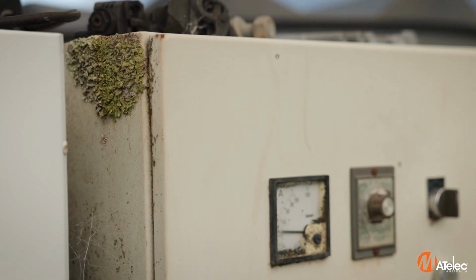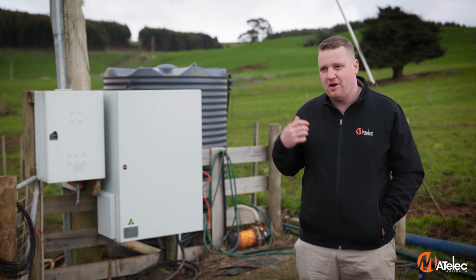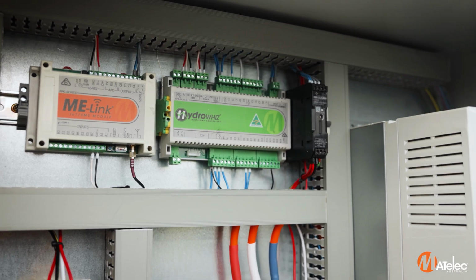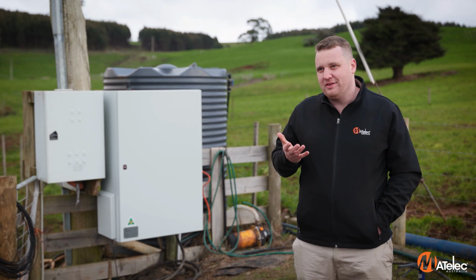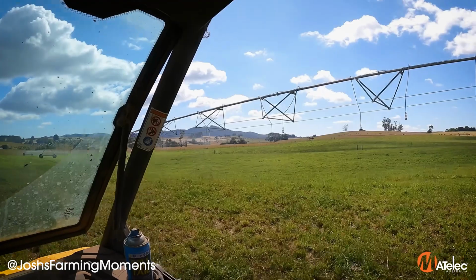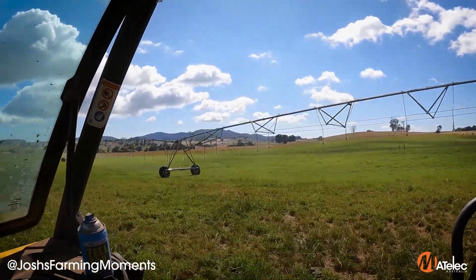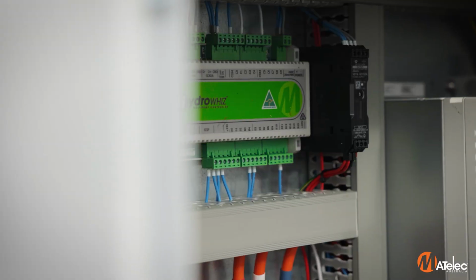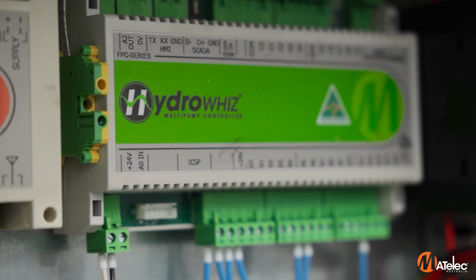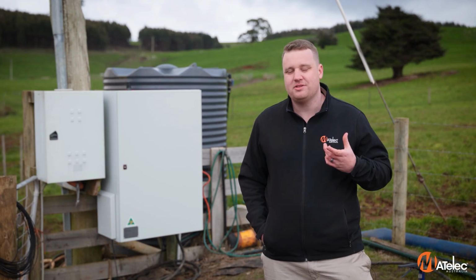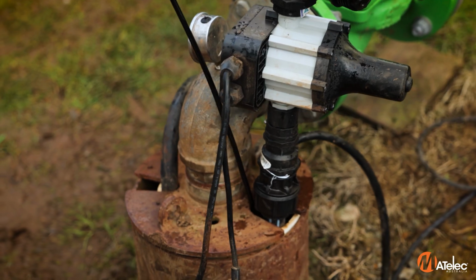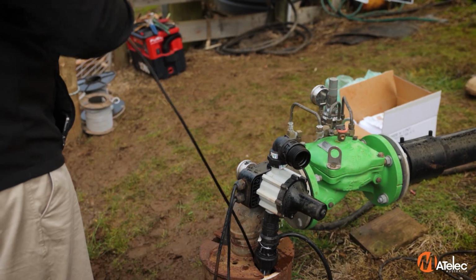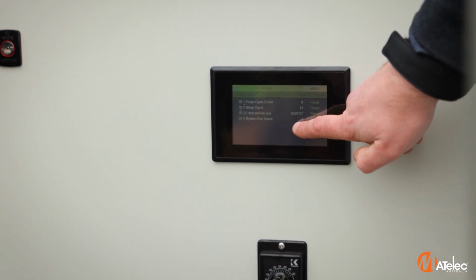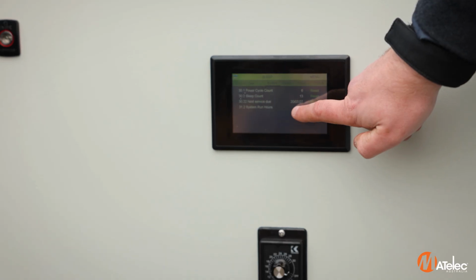The old panel that was here was a very basic setup. It had a manual basic start from a switch on the board, and it had a run-on timer. So now that we've gone to the HydroWHIZ from MATelec, we keep that time clock functionality. But what we also have enabled is the center pivot that feeds from this pump. We can now run an enable signal from the center pivot to here, and that will start the pump automatically when the center pivot calls for it. And it enables us to use the analog input from the level transducer we've got down the bore. In addition to that, you can do all the manual control that we used to do via the screen or through the Propitect platform remotely.